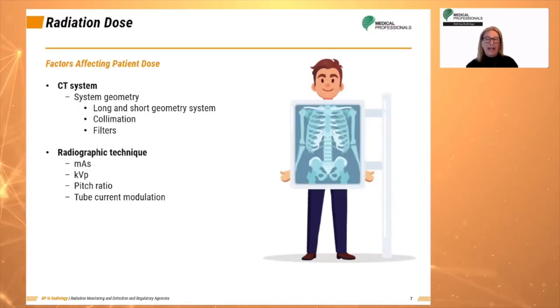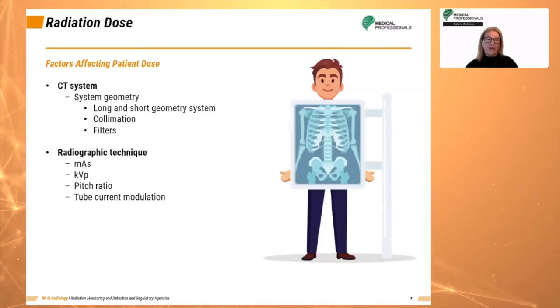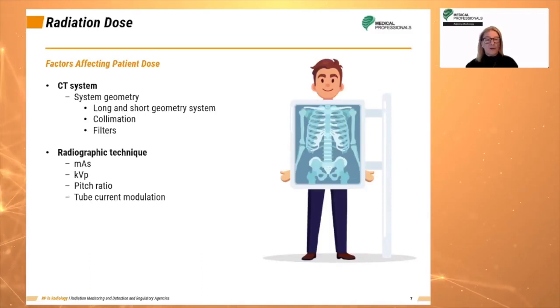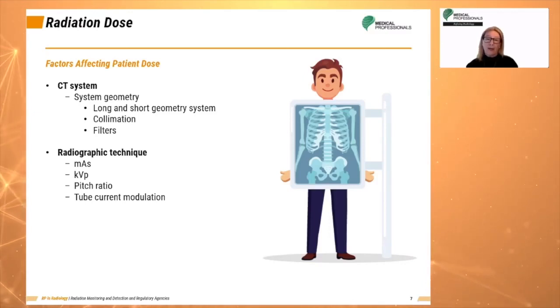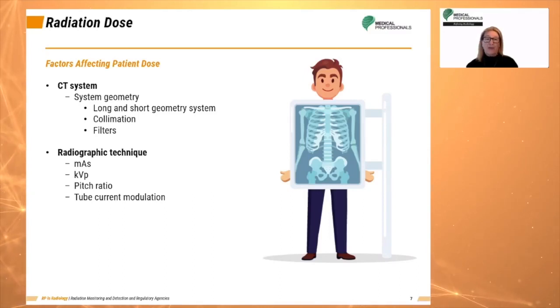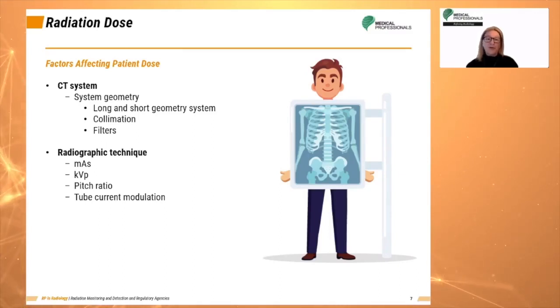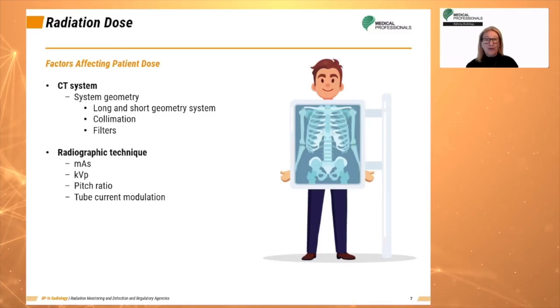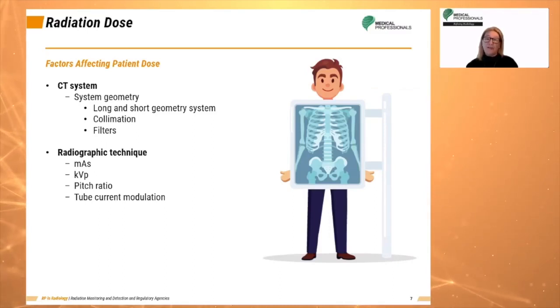Looking at system factors and technologist-controlled factors that affect patient dose: short geometry increases the concentration of photons per unit area and increases patient dose, though an advantage is the reduction of noise. Long geometry, where the source-to-skin distance is longer, results in less patient exposure. Due to the inverse square law, the intensity of radiation varies inversely with the square of the distance from the source.